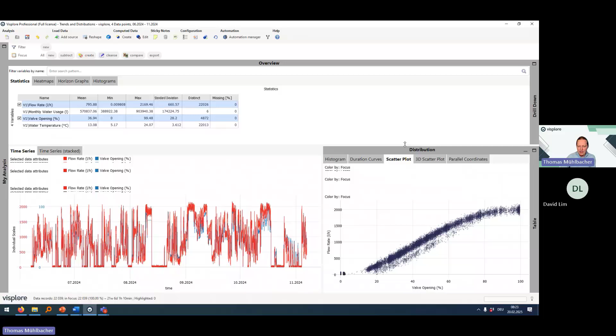For example, a scatter plot. This is an XY plot like we saw before, valve position on X, and flow rate on Y. Here we already see that these two sensors mostly correlate as expected, but there are also some kind of drifting points down here. So this already confirms at first glance something was happening with this valve.